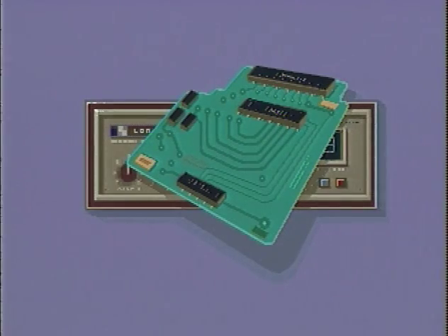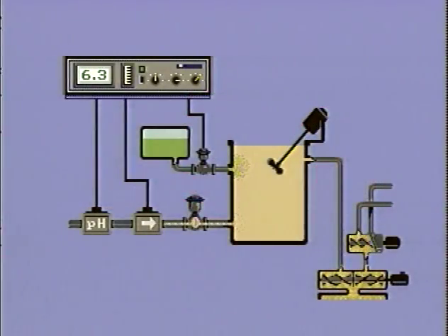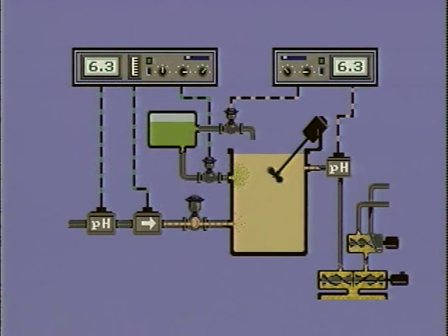In practice, feed-forward is rarely used alone because there is no means of verifying that it is performing as desired. In the chemical plant, a feedback loop with adaptive control was added to monitor the pH and compensate before a variance could introduce a disturbance in the process. Feed-forward control maintained the pH at the proper value most of the time, but the feedback control loop was needed to correct for any deviation in the required pH.